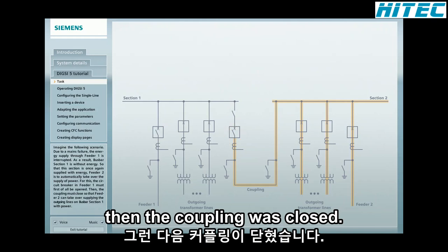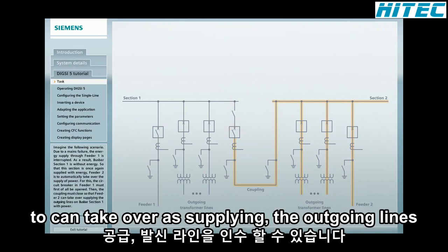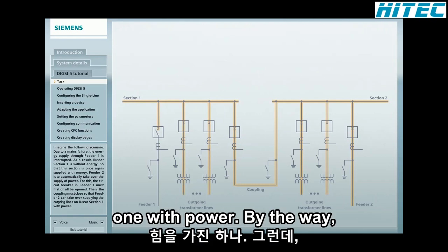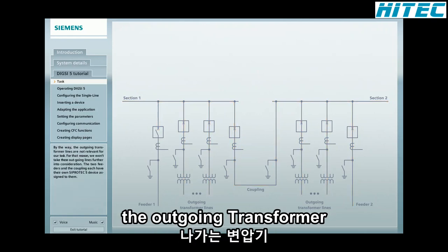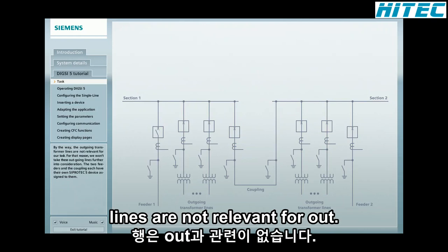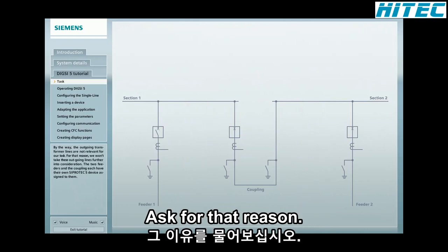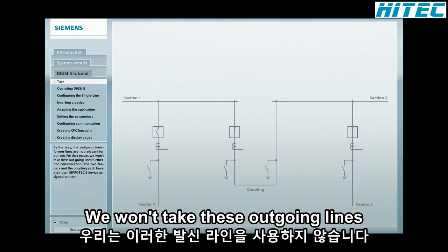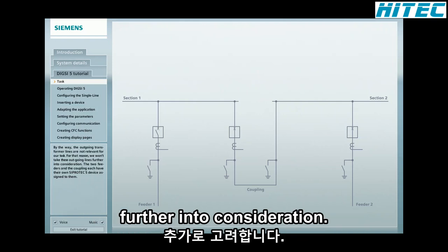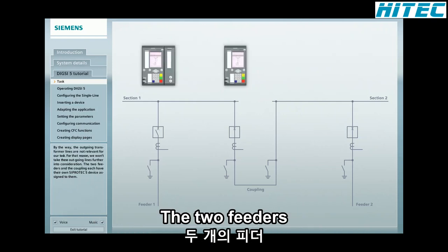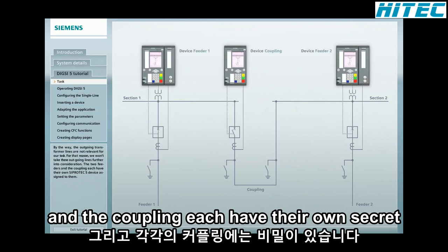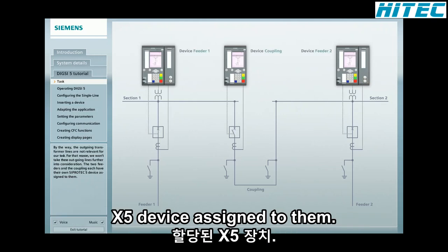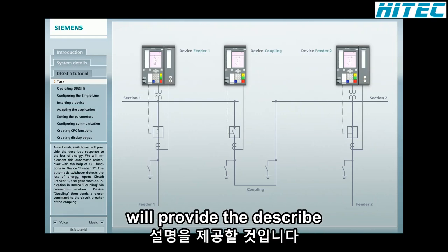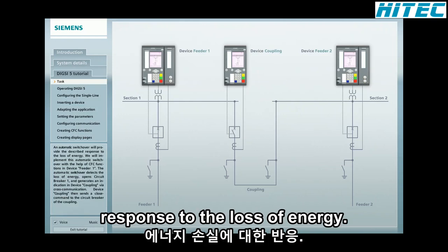Then the coupling must close so that feeder 2 can take over supplying the outgoing lines on busbar section 1 with power. By the way, the outgoing transformer lines are not relevant for our task. For that reason, we won't take these outgoing lines further into consideration. The two feeders and the coupling each have their own SIPROTEC 5 device assigned to them.